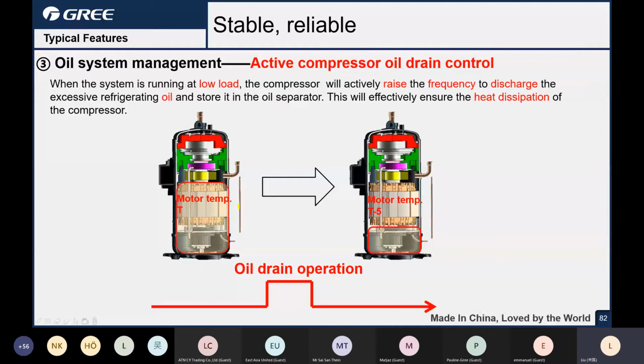I already introduced that in the compressor there is a pump, right? There is a pump and a pipe inside for the oil discharge. If there is too little oil, it may cause a lubricating problem. However, if there is too much oil, is that good for the compressor? No, right? If too little oil, that will cause wear of the compressor. But if too much oil inside, it will also cause some problems, because the oil will circle the winding, circle the motor, and the oil is a very good insulation of the heat.